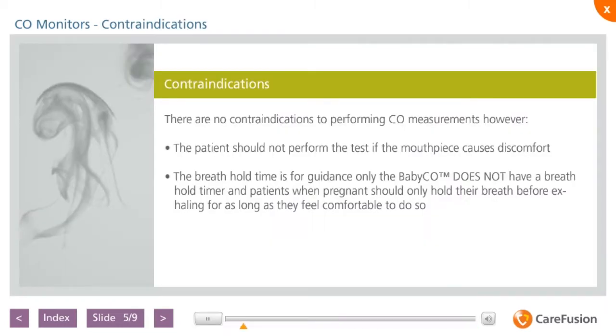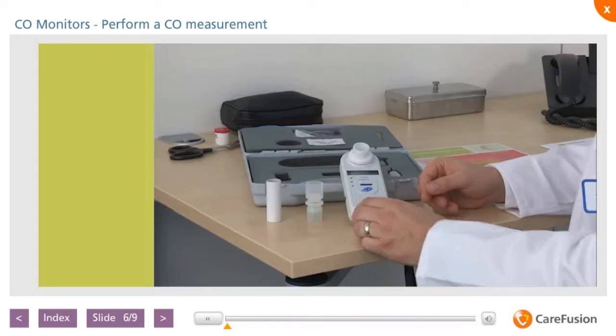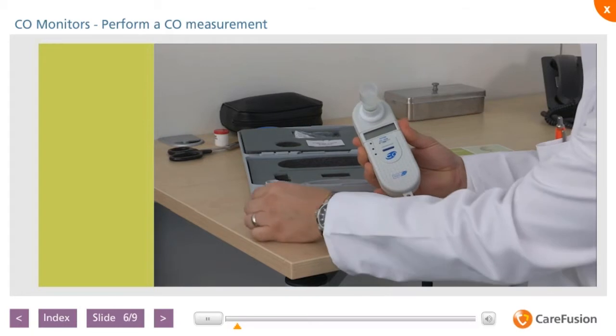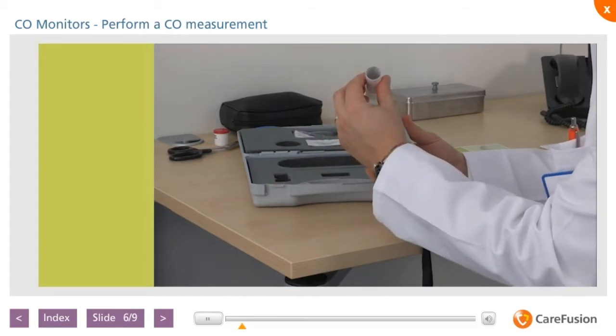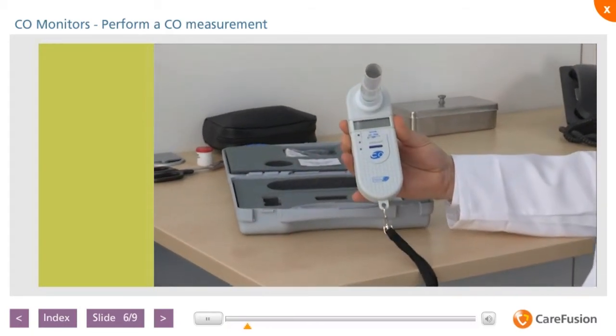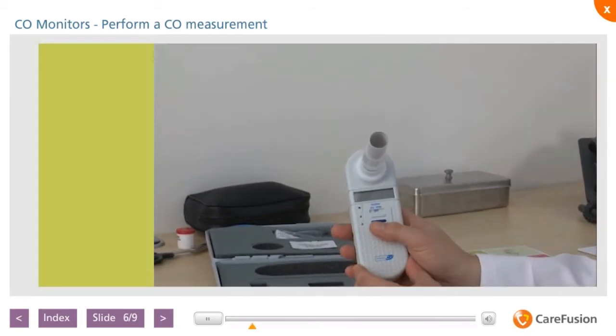There are no contraindications to performing CO measurements, however, the patient should not perform the test if the mouthpiece causes discomfort. The breath hold time is for guidance only. The BabyCO does not have a breath hold timer, and patients who are pregnant should only hold their breath before exhaling for as long as they feel comfortable doing so. Before performing a test on the MicroCO, ensure that the one-way valved mouthpiece adapter and a clean new disposable mouthpiece are inserted into the device before turning it on.